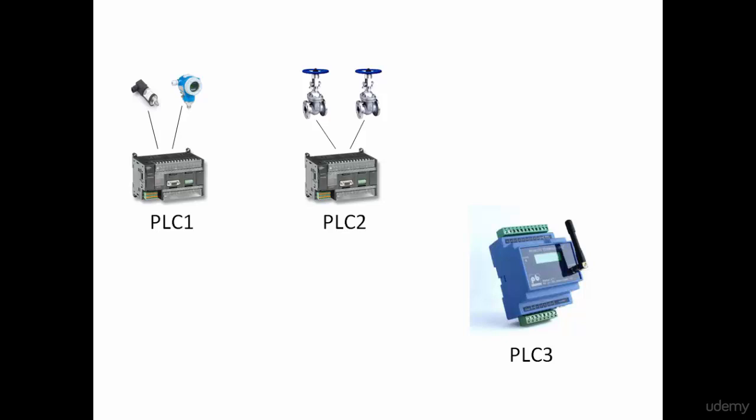So our problem then is to connect PLC3 to PLC1 and 2 using RS485 and then configure all three PLCs so that PLC3 constantly reads the latest values of pressure, temperature, and valve positions from PLCs 1 and 2. PLC3, then having these values, will transmit them periodically back to the marine base for data capture and analysis. So that, folks, is the problem we're going to solve at the end of this course. So from here on, as we go through the theory and practical details of Modbus and RS485, I want you to constantly keep in mind the problem that we are trying to solve. Great.